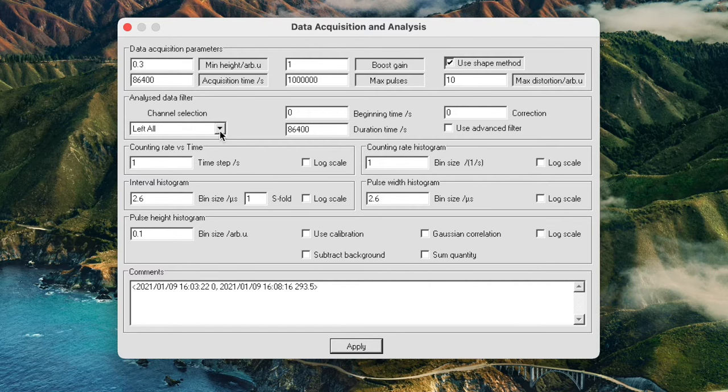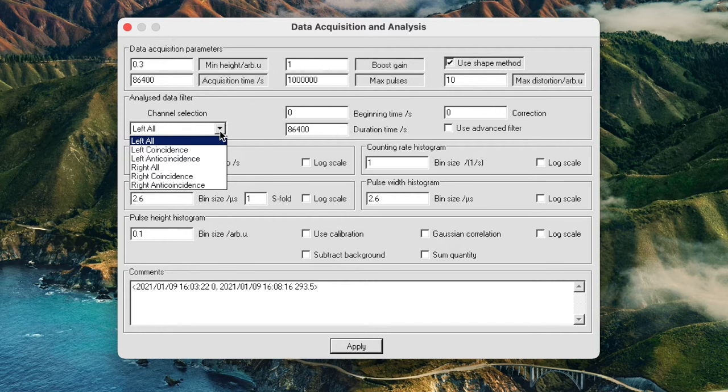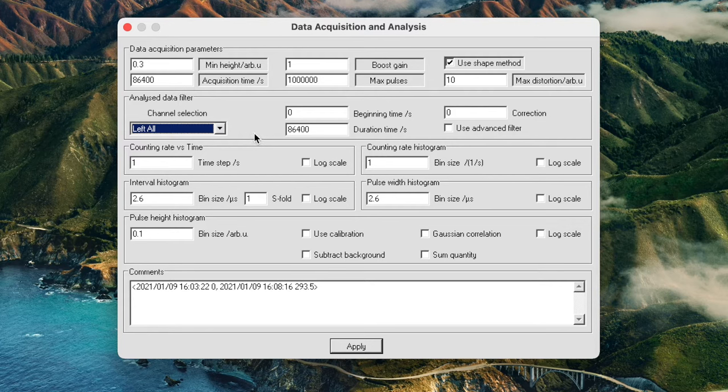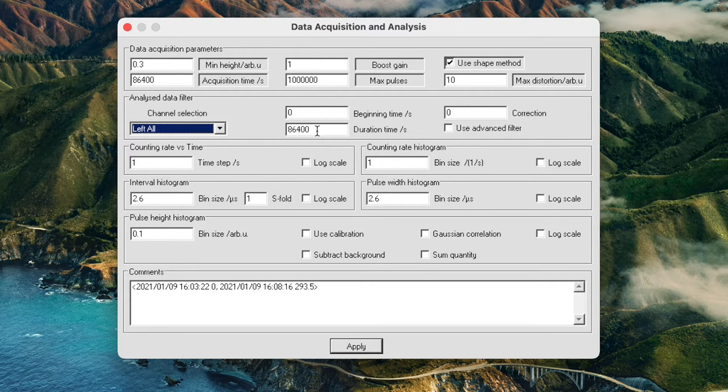The next field here is the channel selection. We are operating at the moment with one spectrometer and one detector through the left channel so we are recording the left channel. But if you were using multiple detectors and multiple spectrometers then you would be using both the left and the right stereo channel of the sound card. These parameters are simply the beginning time and duration time in seconds so you can limit your experiment to record 1000 seconds or 10,000 seconds or any number of seconds that you wish and then the software will stop after that time.